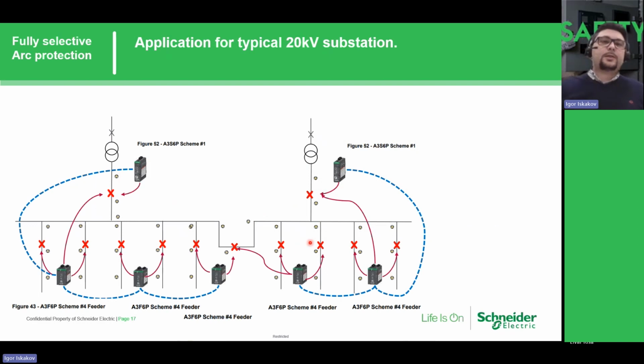So here is a typical single line diagram of the substation. I just tried to make it typical for the Nordic zone, where we don't have a lot of feeders, less than 10, and we have 2 transformers which can supply their parts. So this is a typical scheme for a 20 kilovolt substation. And here you see where the units are situated.